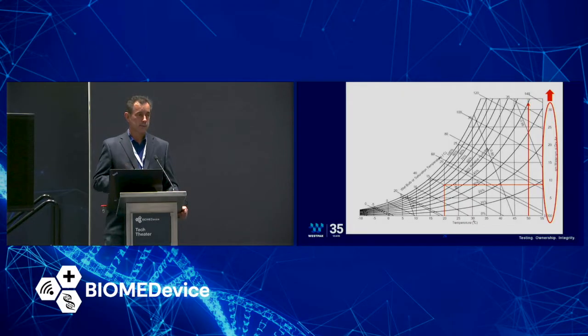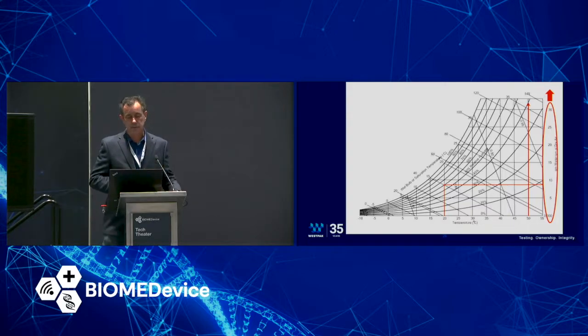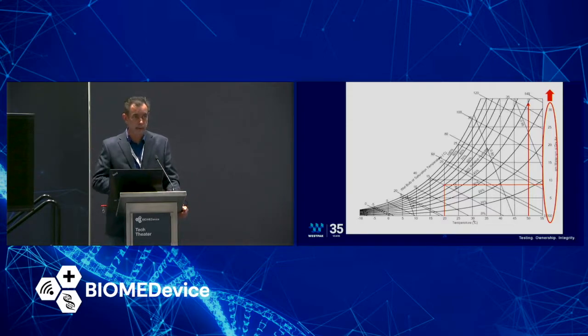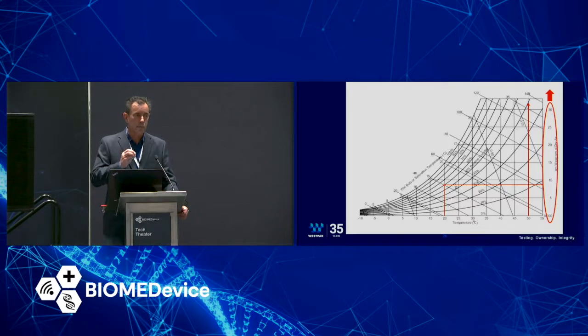Is that necessarily bad? Early on when we were doing accelerated aging, we used to put in very high humidities, about 75%. What we noticed was that the poly material, because it was laminated together with a water-based adhesive, would separate — you'd have laminate separations of the material. This was concerning because you'd have to write an NCR and do analysis on it. Then you'd get your real-time samples back and not even see this, leaving you wondering what happened.